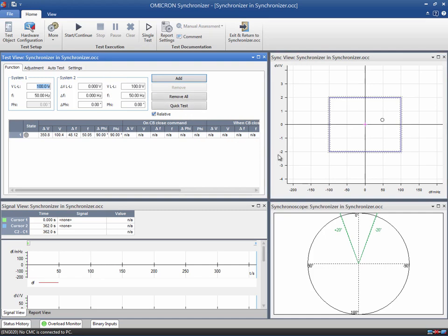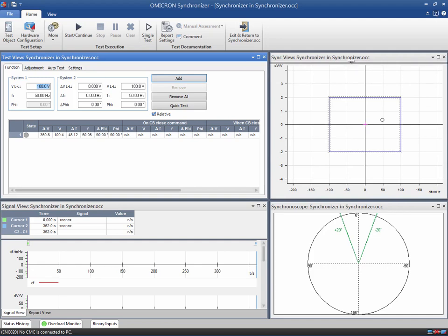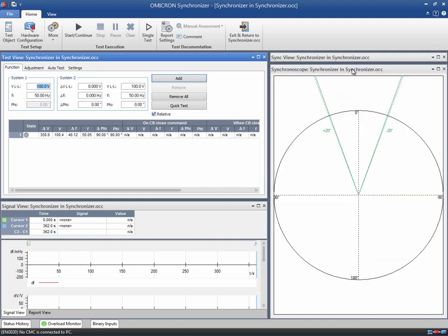The Synchronoscope displays the phase difference between System 1 and System 2. The solid green lines represent the allowable phase difference, while the green dashed lines symbolize the tolerances entered in the test object.